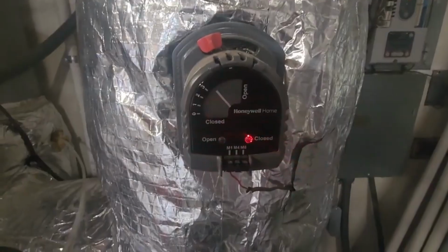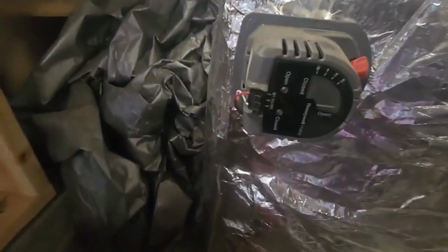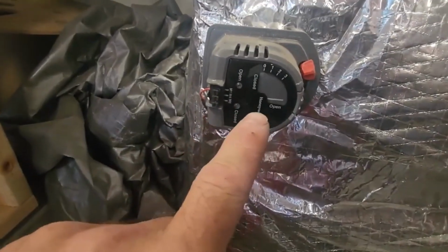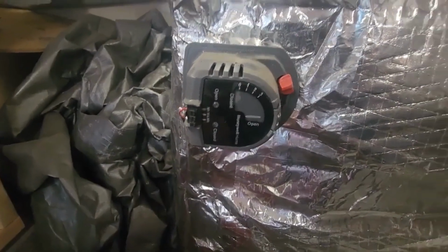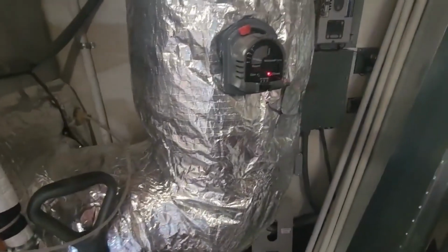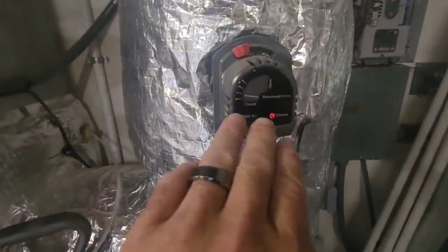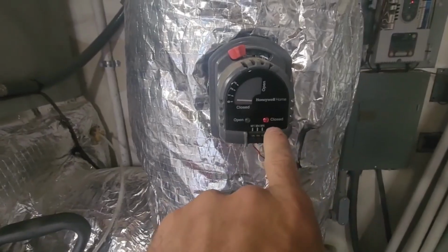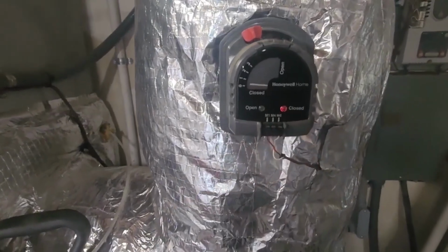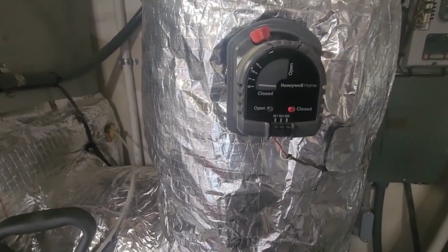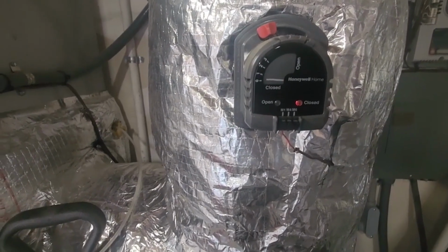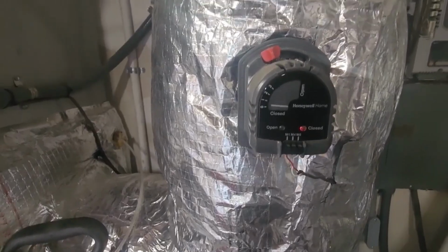Okay guys, just waiting for this upstairs damper to close all the way. Our upstairs is wide open, so let's just let that shut. It's still going to keep it only in first stage, so our fan's still going to stay low. As long as that light's blinking, it's still trying to close. And yeah, we are there. It is now closed. Let's check our static.